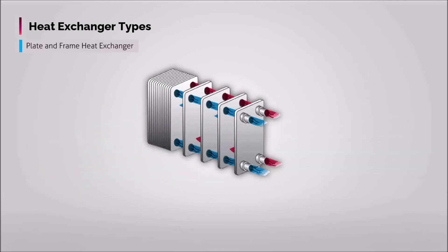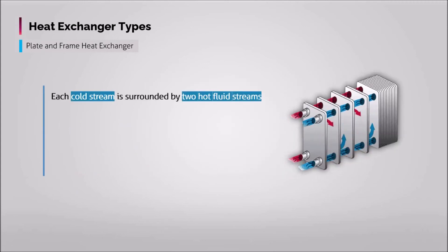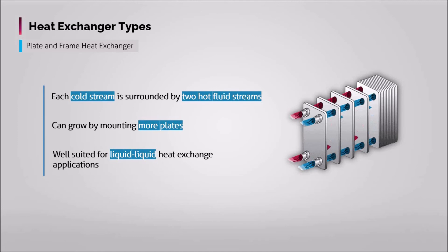Plate and frame exchangers, also called plated exchangers, consist of a series of plates with corrugated flat flow passages. The hot and cold fluids flow in alternate passages, so each cold fluid stream is surrounded by two hot fluid streams, resulting in very effective heat transfer. Plated exchangers can also expand with increasing demand by simply mounting more plates, and they are well suited for liquid-to-liquid exchange when the hot and cold fluid streams are at about the same pressure.